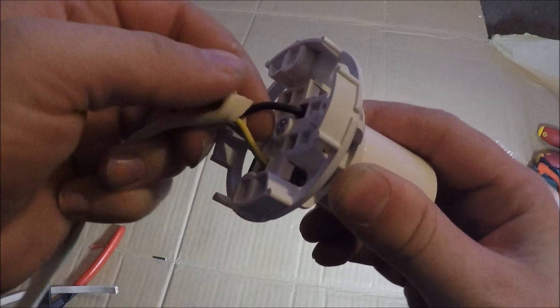Now do these screws up nice and tight and do a pull test every time you fit off a cable in them just to make sure that it's clamped in properly. The other thing you want to ensure is that when you're screwing down the screw, look on the inside of here and just make sure it's clamping down onto the copper itself and not onto the insulation.